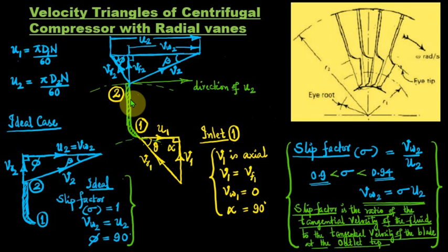See, the radial vane is shown over here. Out of 4 blades, I have taken one, so that one vane is shown over here. See, a slight bend at the inlet tip. It's like this, so you can draw like this. The outer radius is shown, the inner radius is shown, and this is the triangle. This is the inlet velocity triangle, and V1 is equal to Vf1, Vw1 is 0 and alpha is 90. You know that theta is the vane angle, and the various terminologies, the nomenclature we know already.